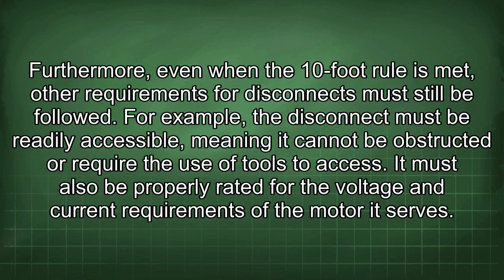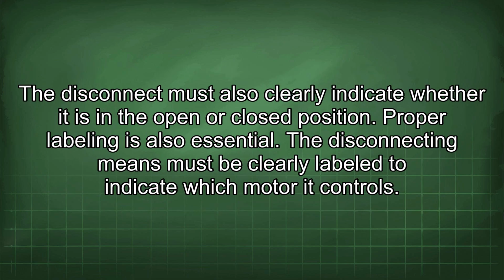Furthermore, even when the 10-foot rule is met, other requirements for disconnects must still be followed. For example, the disconnect must be readily accessible, meaning it cannot be obstructed or require the use of tools to access. It must also be properly rated for the voltage and current requirements of the motor it serves. The disconnect must also clearly indicate whether it is in the open or closed position.